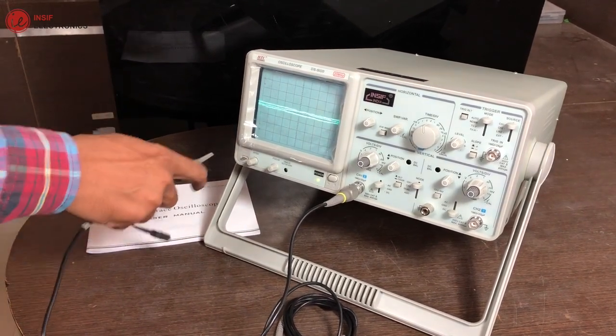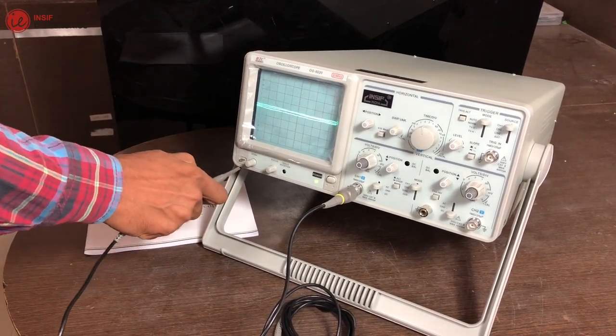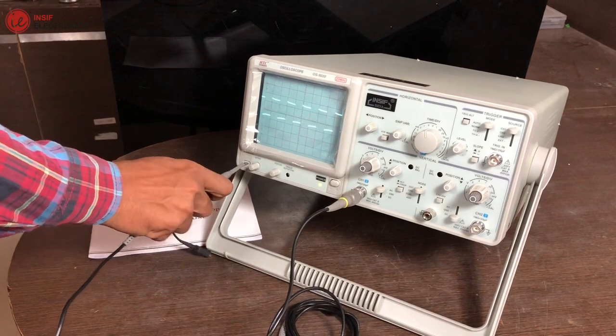Now, connect the input of the probe to the calibrating signal provided on the CRO, and observe the waveform.